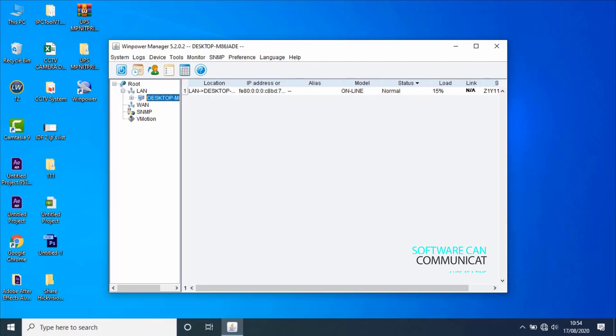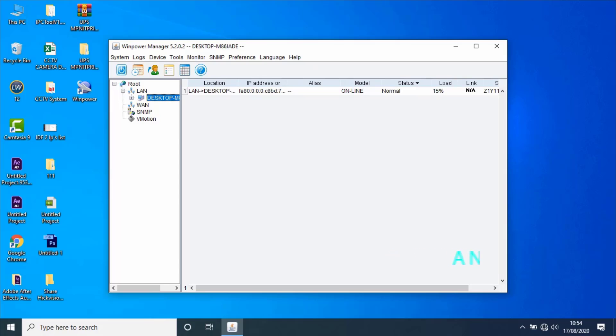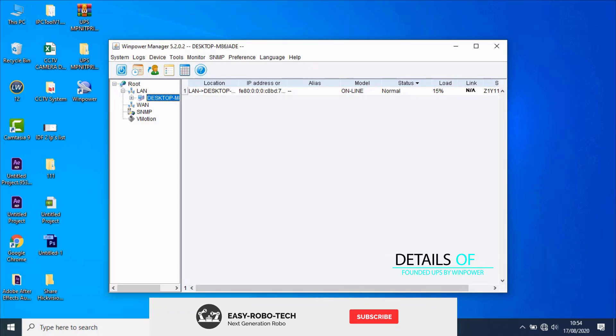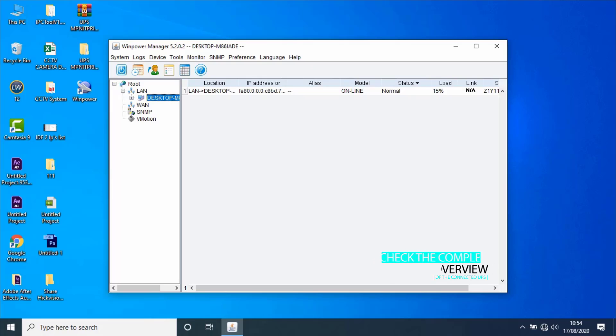Software can communicate with up to 4 UPS via RS-232 port at the same time. As you can see on the software interface window, a UPS has been found. It's showing all the details of the found UPS, such as location, LAN or WAN, IP address or MAC address, mode — offline or online — status — normal or faulty — and connected load in percentage.